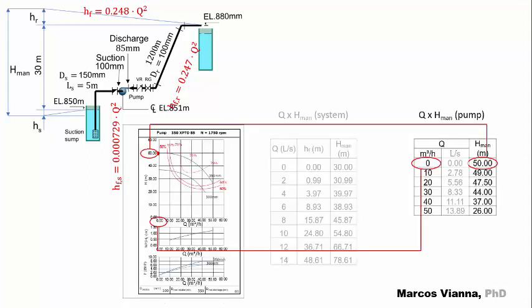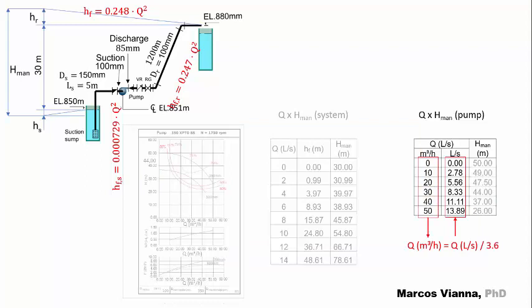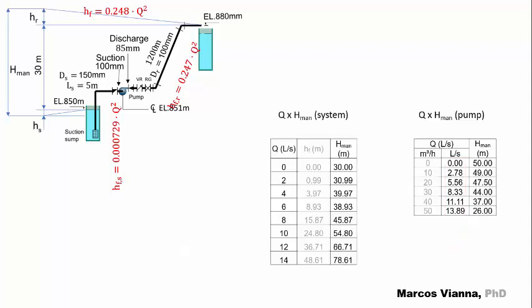Now, we draw another table containing the values of Q and H extracted from the pump curve. Let's transform the Q values from cubic meters per hour to liters per second. Now, we have the data to draw the characteristic curves of the pump and the system.